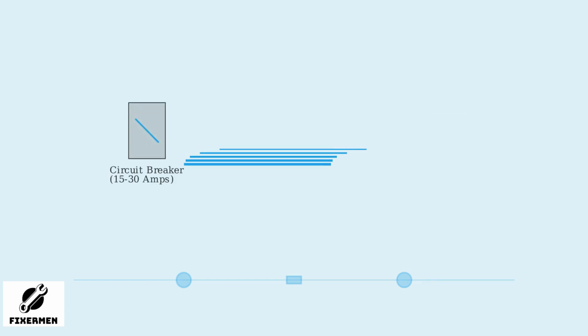When the AC compressor starts, it requires a massive surge of electricity, up to 5 to 10 times more than its normal operating current. This inrush current can overwhelm the electrical system. This graph shows the inrush current spike at startup. The peak marked with an arrow represents the surge that can trip breakers. Circuit breakers are designed to protect electrical systems by tripping when current exceeds their rated capacity, typically 15 to 30 amps for residential AC units.